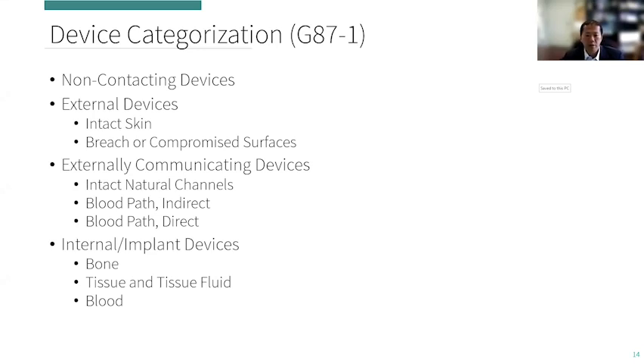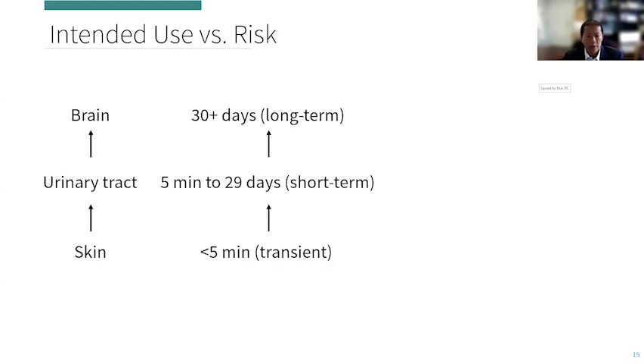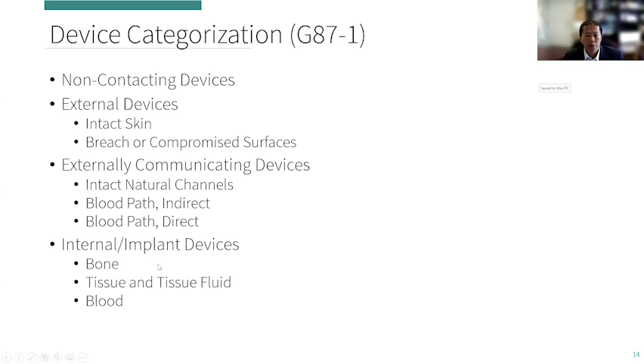We also have externally communicating devices — these contact from the external to the internal portions of the body, and this can happen through intact natural channels. For example, a contact lens or urinary catheters that go from the outside to the inside of the body. We also have other types of externally communicating devices, such as those with indirect contact with the blood path, where it contacts one point and is a conduit for fluid entry into the blood path. For example, this would include things like blood administration sets.